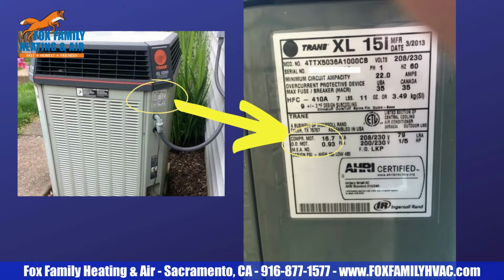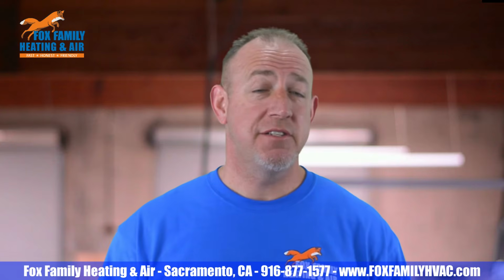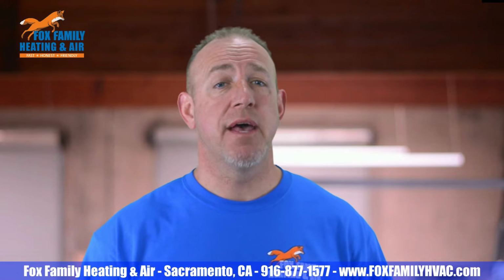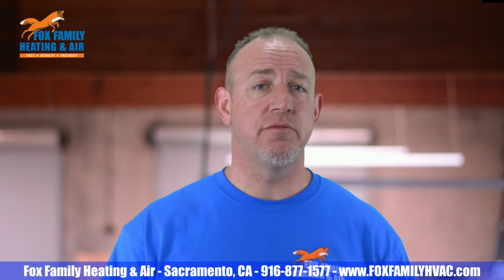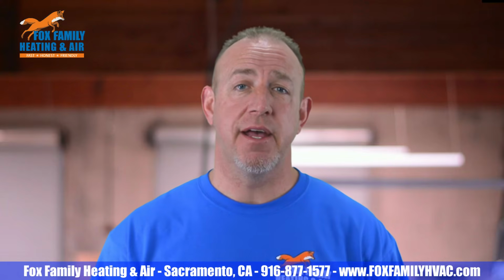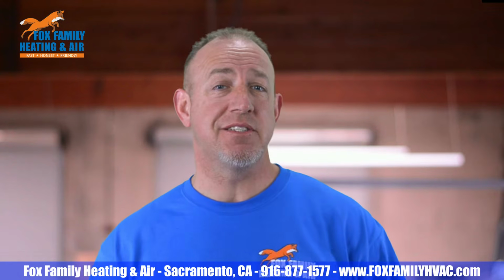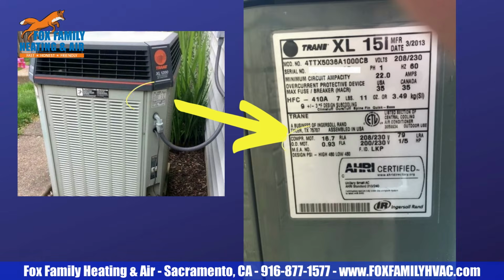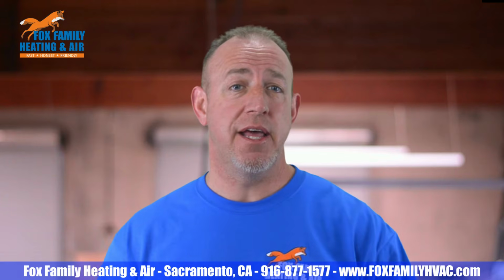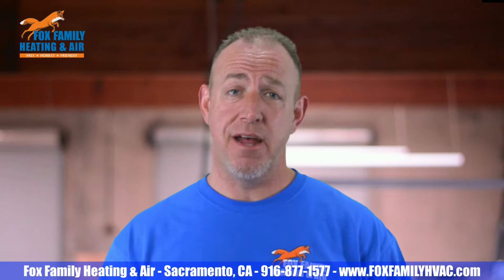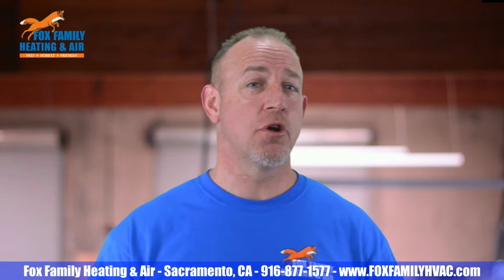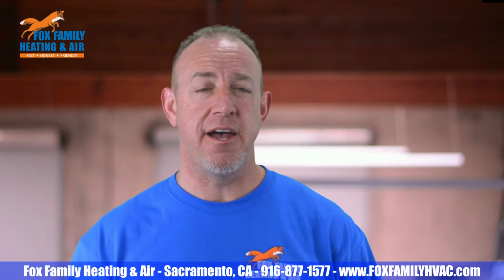Are there high run load amps compared to the RLA spec on the data plate? Here's how to tell. Use your amp clamp on the common wire, no closer than 4 inches or so to the compressor. On a typical 85-degree day, the amps are usually going to be running at about 60 to 70% of its RLA spec on the data plate. Even closer to that RLA number on the hottest days of the year, right?